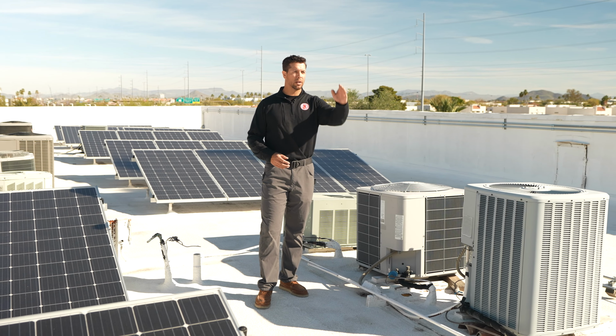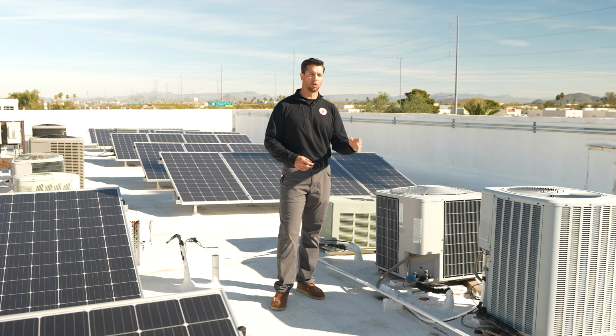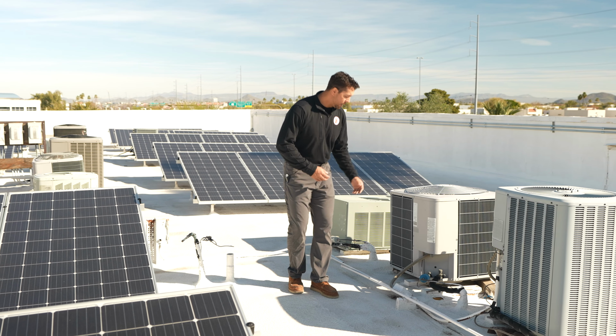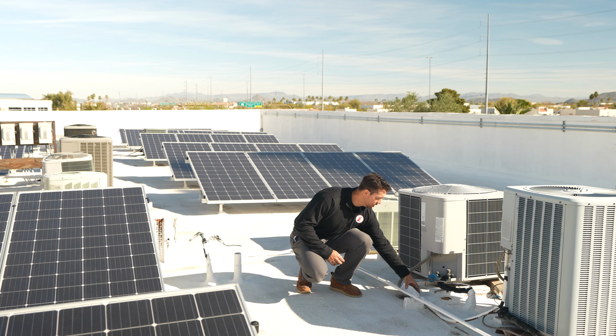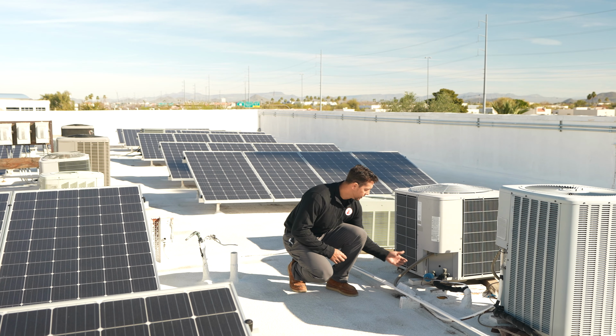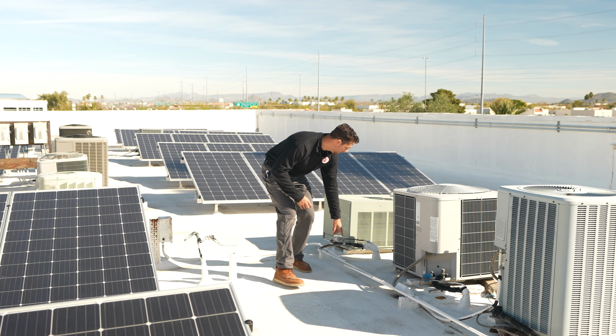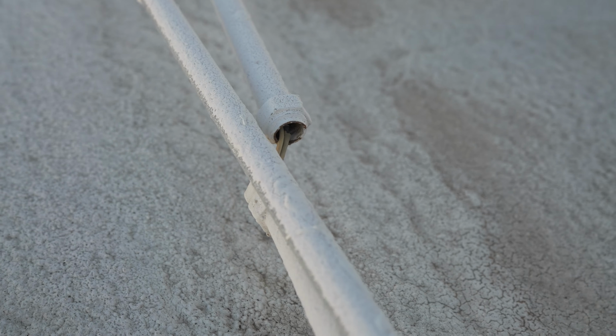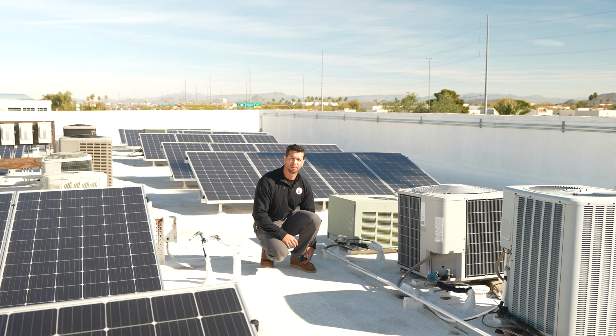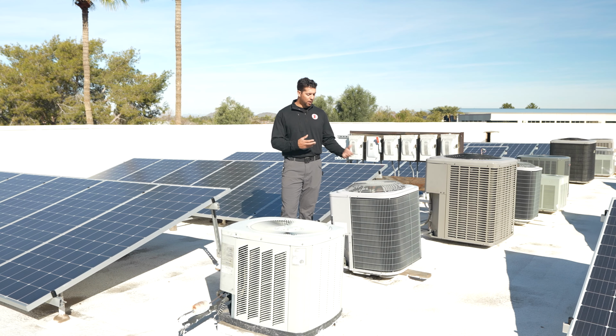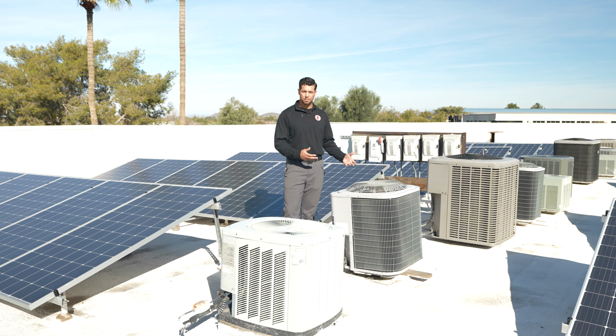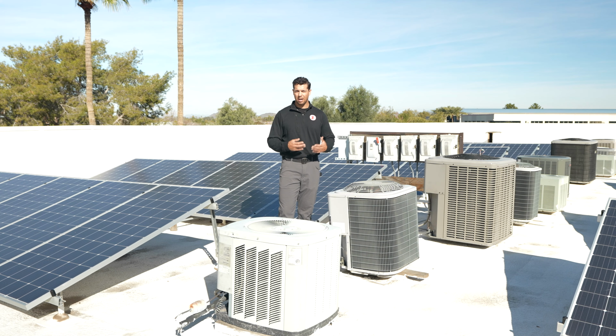Here we have conduit running to each unit from our service disconnects. And here you can see it fell off of its support, which caused an opening at the next connector - an electrical defect and something we'd definitely want to note in our report. We also found multiple units that were out of level. Now, it's not a requirement to carry a spirit level.